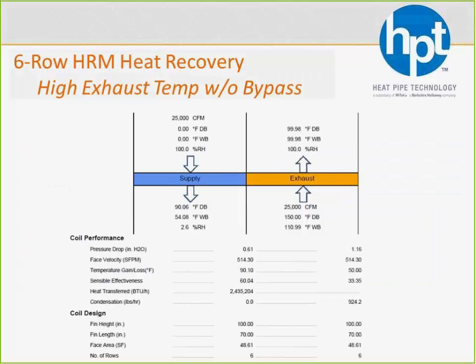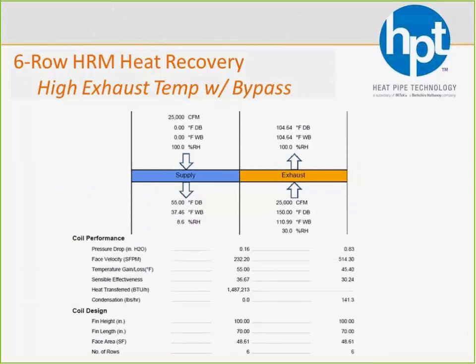So if we take a look at that, and again, this is right out of Select Plus, and you run these scenarios, and let's say it's 0 degrees outside, 150-degree air, we're actually going to be about 60% effective at this condition, which means we're going to heat up that air by 60% of that 150-degree delta T, or 90 degrees. Of course, if they want 55-degree air, 90 degrees is going to be way too hot. So what do you do? You put a bypass damper on it.